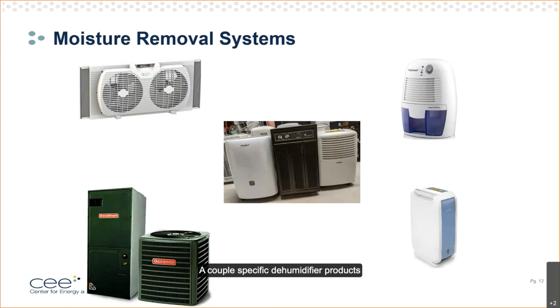A couple specific dehumidifier products I want to go over quickly before we never speak of them again. In the upper right, I show what's called a thermoelectric dehumidifier, sometimes called an electric dehumidifier. These you can identify from their very small size, lightweight, maybe the size of a toaster, and very low price—somewhere around 20 to 50 bucks. They use what's called the Peltier effect to condense moisture, albeit very inefficiently, around 4 to 5% efficiency. They distinguish themselves in that they can only remove ounces of moisture per day—we've been talking in pints, but these have a capacity of ounces. They're usually marketed for cabinet or closet dehumidification. Sometimes, particularly on the internet, you'll find them marketed for dehumidifying occupied spaces. They cannot do this—they're functionally useless for dehumidifying occupied spaces, and are really only reserved for niche situations.